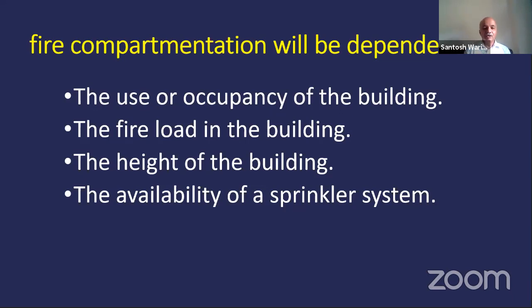Fire load. National Building Code Annexure A gives you the calorific values of different materials, with which you can carry out the fire load calculation for any particular compartment. If the fire load is more, you can distribute the load into different compartments by segregating it. Height of the building is very challenging. The higher you go, the more time you require for evacuation. So in such cases, it is very important to segregate the compartment where the fire is and contain it, so that you get more time for evacuation. The availability of sprinklers. With proper distribution of sprinklers, it is a three-dimensional extinguishing medium. You can cool the fire, contain the fire, and cool down the smoke also.